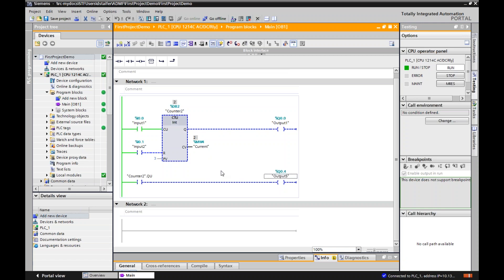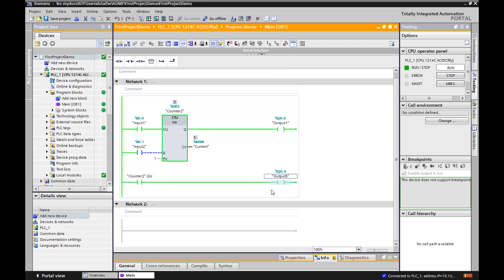And then it goes false. This is only detecting when it changes from false to true to count. So if I leave this on here, it's not going to keep counting. I will show you why that may be a problem if we do an add command. This is why we have counters because it will keep counting every time this goes true. But now, since this current equals this preset, you can see that this Q output is turned on. Same down here, counter two dot QU. This output is now turned on.